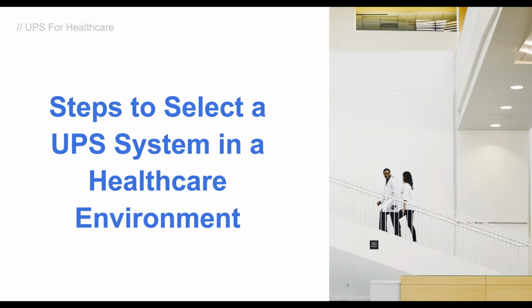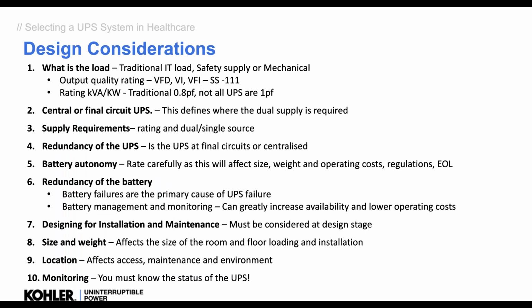Okay, so getting towards the end, we've got to look at what the load is and what quality of supply we need from the UPS. We have to make sure we understand the difference between a kVA and a kilowatt. Most traditional UPSs used to be sized at 0.8 power factor. Now it's variable, it might be 0.7 to 1, so you have to be very careful what you're asking for from your supplier. Central or final circuit UPS defines where the dual supply is required. If we need dual supply at final circuit, that might mean having 2 central UPSs feeding those supplies.